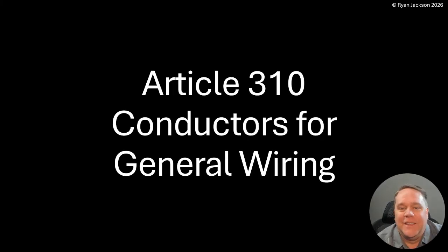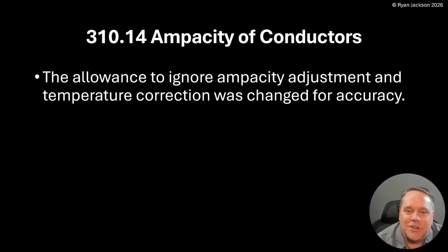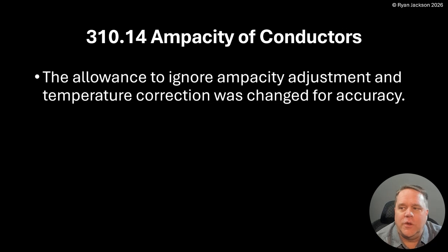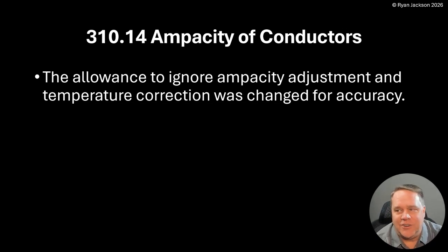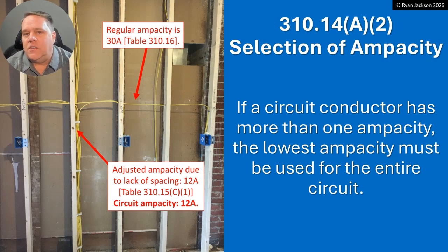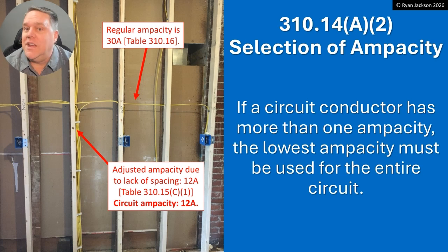310.14 is kind of the baseline rule in Article 310. Let's take a look at what Panel 6 did — I actually think they fixed a problem that even I never caught. I spent a lot of time in 310.14 and this rule never dawned on me. Article 310: Conductors for General Wiring. 310.14: Ampacity of Conductors. The allowance to ignore ampacity adjustment and temperature correction was changed for accuracy. We're going to be talking about 310.14(A)(2).